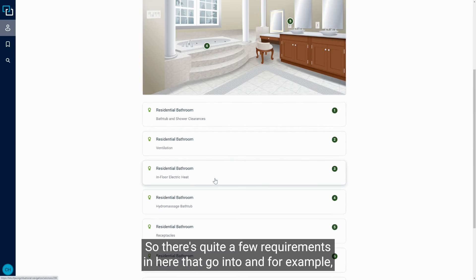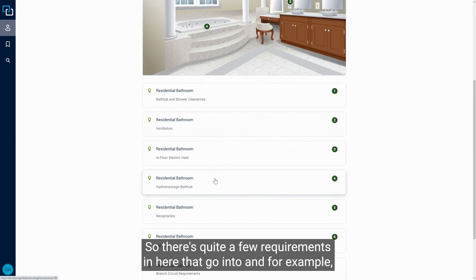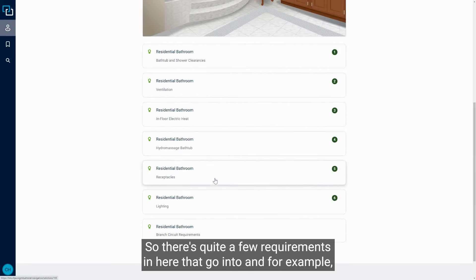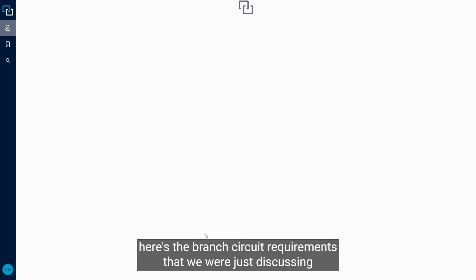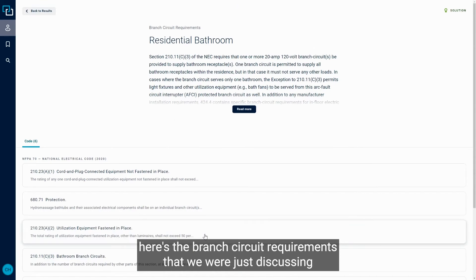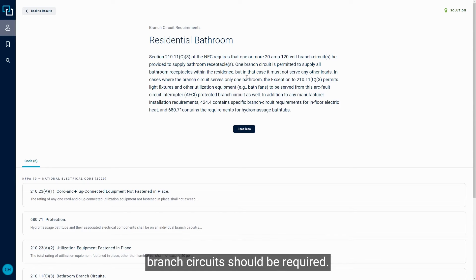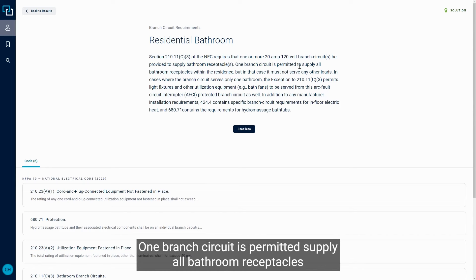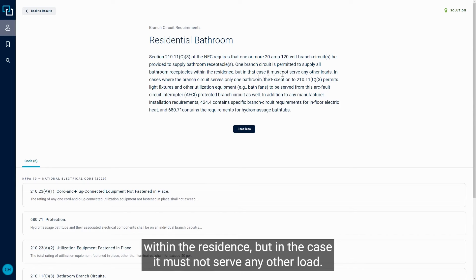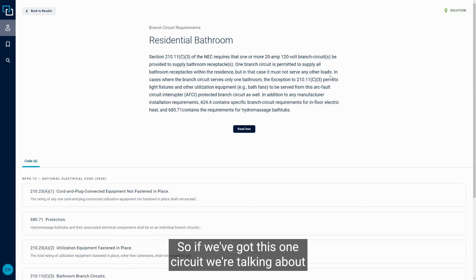So there's quite a few requirements in here that go into, and for example, here's the branch circuit requirements that we were just discussing in 210.11.C.3. We've got one or more 20 amp branch circuits should be required. One branch circuit is permitted to supply all bathroom receptacles within the residence, but in the case, it must not serve any other load.